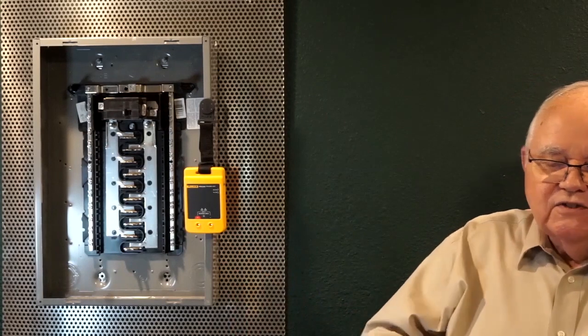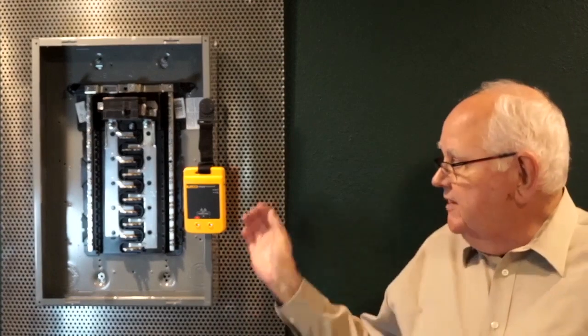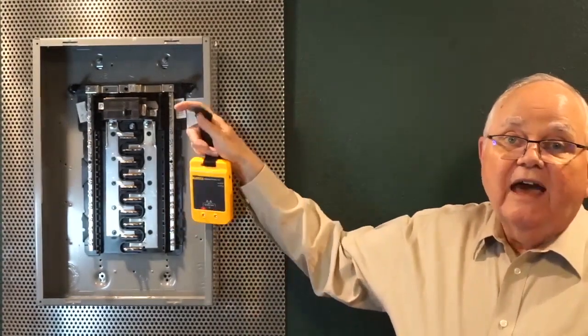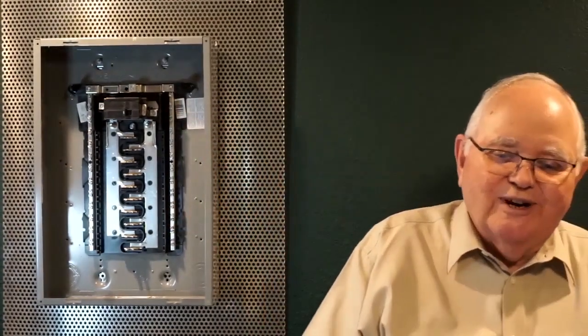Once I create the electrically safe work condition and I've verified that this equipment is safe to work on, and I did in fact lock out and tag out the correct breaker upstream, I can now go ahead and take off all of my PPE, except what's required for my normal PPE in my company to wear, and I can go to work on this piece of equipment then.